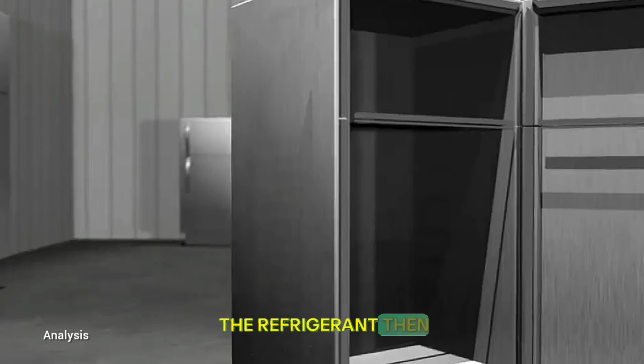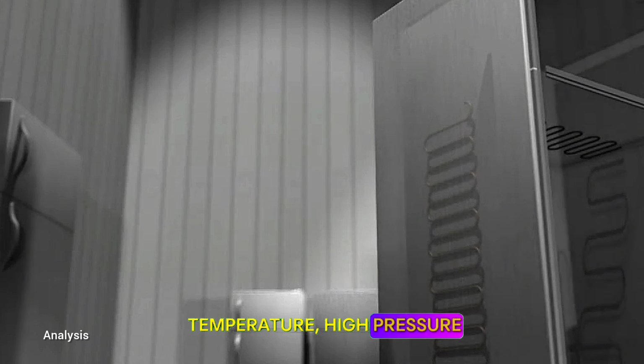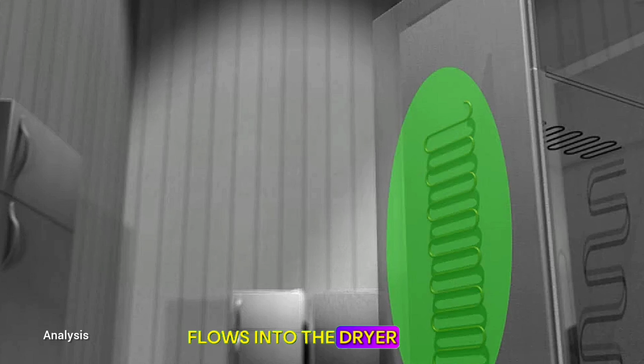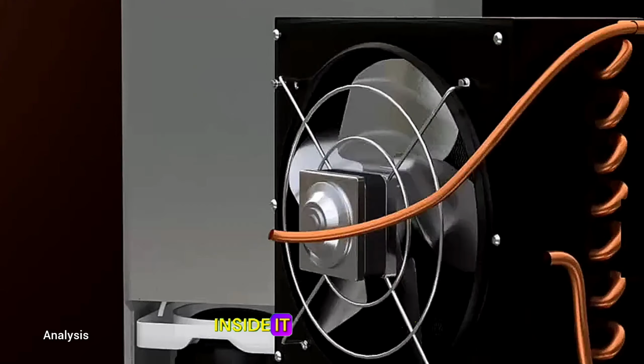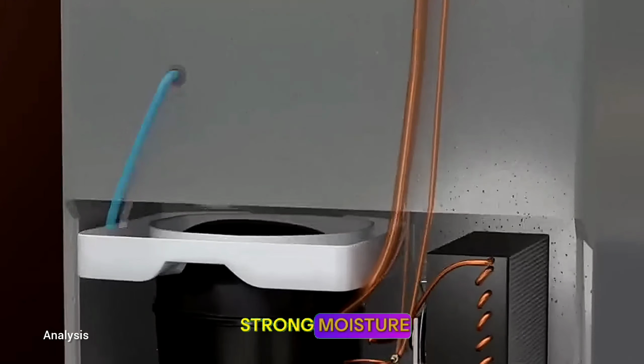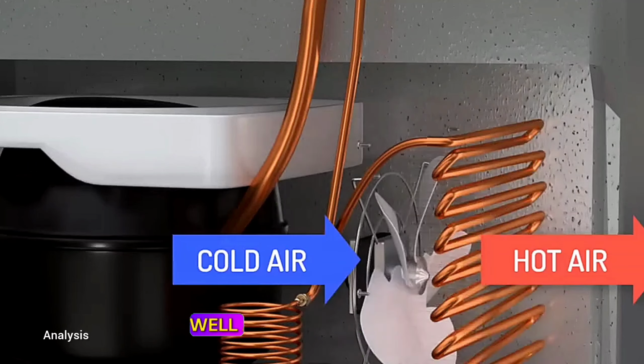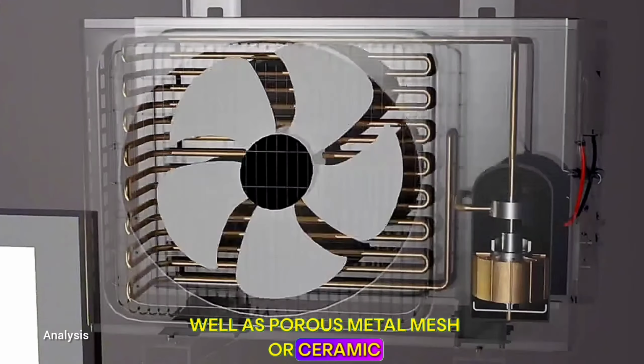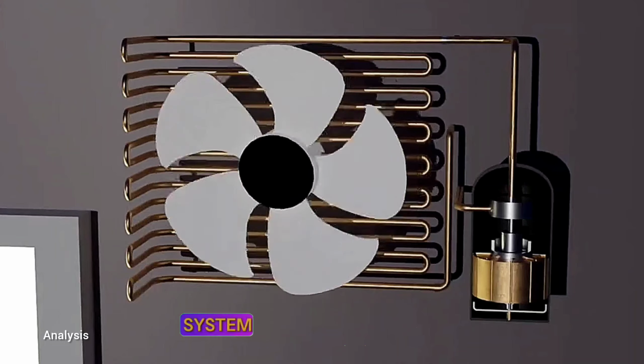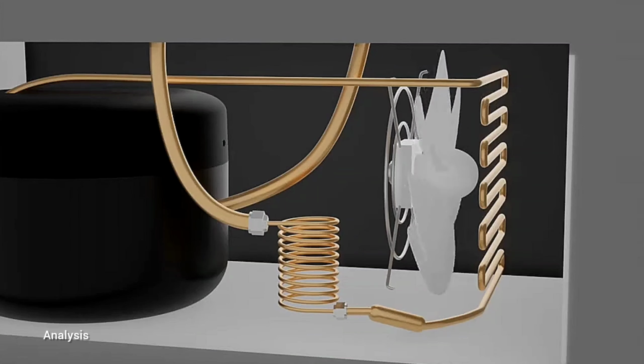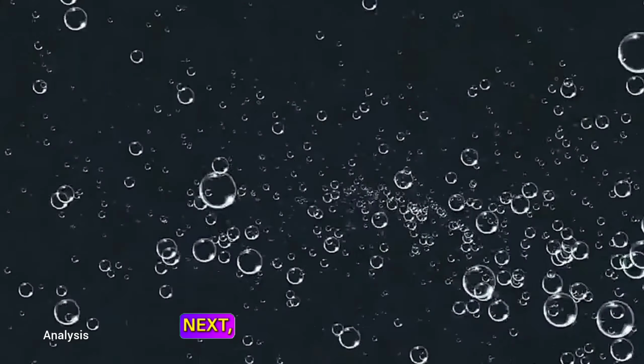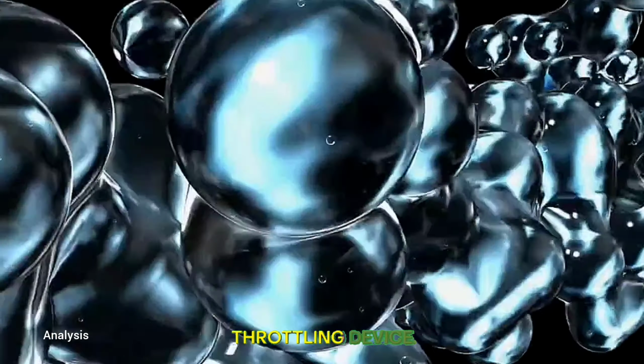The refrigerant then becomes a high-temperature, high-pressure liquid and flows into the dryer filter. Inside it are desiccant pellets with strong moisture absorption capacity, as well as porous metal mesh or ceramic filters, which protect the cooling system from damage caused by moisture and impurities. Next, the refrigerant enters the throttling device.